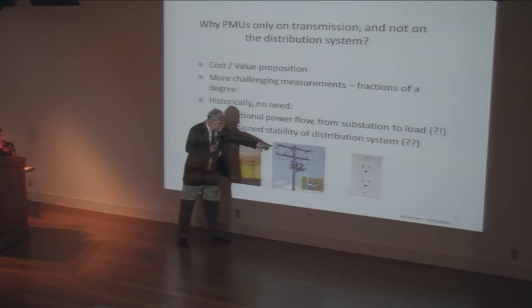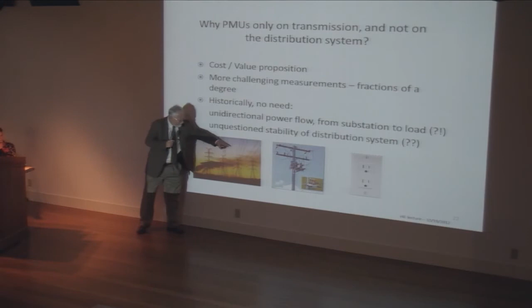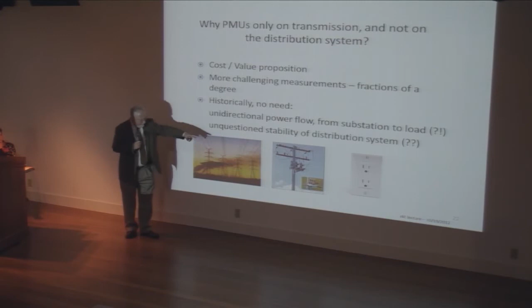The other challenge on distribution is that, as Sascha said, all of the phase angles are introduced by the inductance of these conductors, and the inductance is roughly linearly proportional to the distance between the conductors. It's an order of magnitude bigger here than there. So the inductances we're dealing with on the distribution system are a couple to three orders of magnitude smaller, which means the phase angle differences are also three orders of magnitude smaller. A thousandth of a degree is interesting, as opposed to a degree on these systems.